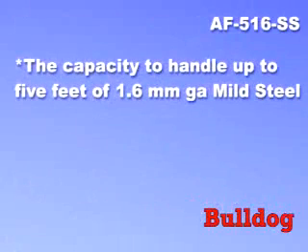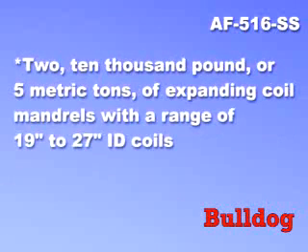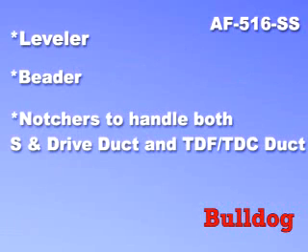The capacity to handle up to 5 feet of 1.6 millimeter gauge mild steel. A unitized single piece frame. Two 10,000 pound or 5 metric ton expanding coil mandrels with a range of 19 inch to 27 inch ID coils. Leveler, beader, and notchers to handle both S and drive duct and TDF-TDC duct.